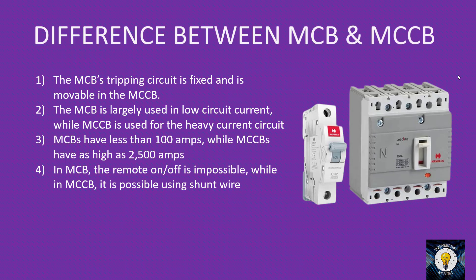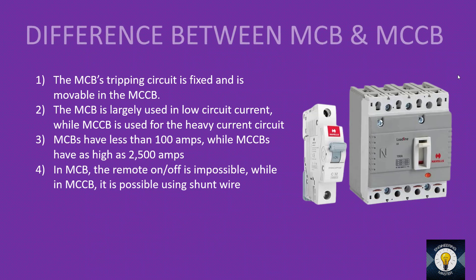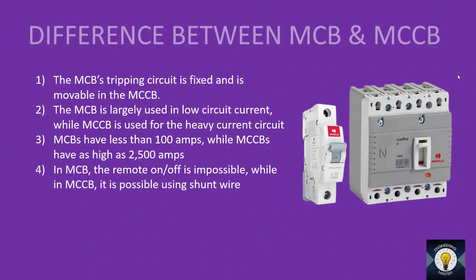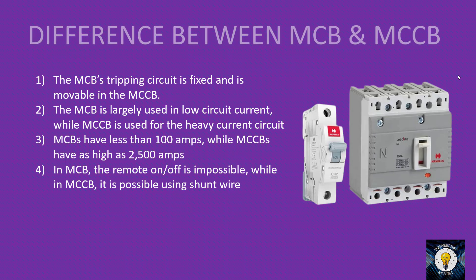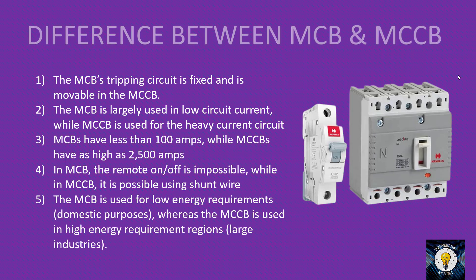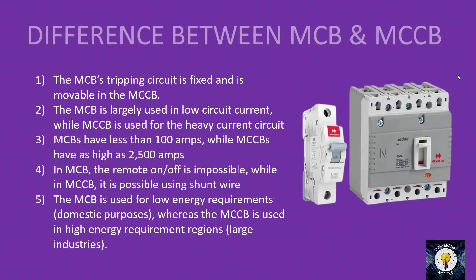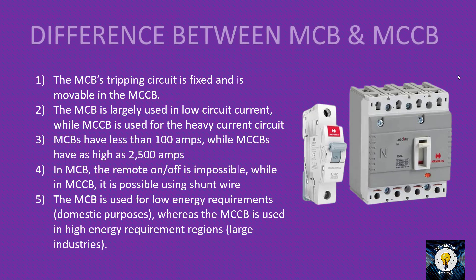In MCBs, remote on/off is not possible as it is not inbuilt. In MCCBs it is possible using a shunt wire. That means if the panel is in one location and you want to operate it from another location, you can do it in MCCB using a shunt wire and an emergency push button switch. The fifth difference is that MCBs are used for low energy requirements like domestic purposes, while MCCBs are used for high energy requirements like industrial purposes.